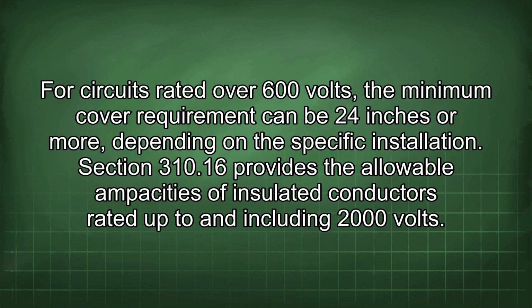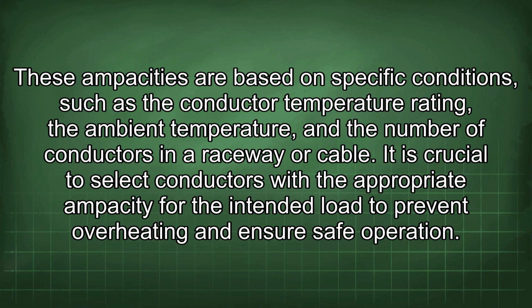For circuits rated over 600 volts, the minimum cover requirement can be 24 inches or more, depending on the specific installation. Section 310.16 provides the allowable ampacities of insulated conductors rated up to and including 2000 volts. These ampacities are based on specific conditions, such as the conductor temperature rating, the ambient temperature, and the number of conductors in a raceway or cable. It is crucial to select conductors with the appropriate ampacity for the intended load to prevent overheating and ensure safe operation.